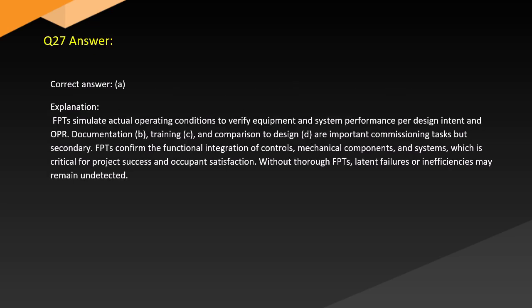Answer. Correct answer: A. Explanation. FPTs simulate actual operating conditions to verify equipment and system performance per design intent and OPR. Documentation. B, training, C, and D, comparison to design, are important commissioning tasks but secondary. FPTs confirm the functional integration of controls, mechanical components, and systems, which is critical for project success and occupant satisfaction. Without thorough FPTs, latent failures or inefficiencies may remain undetected.